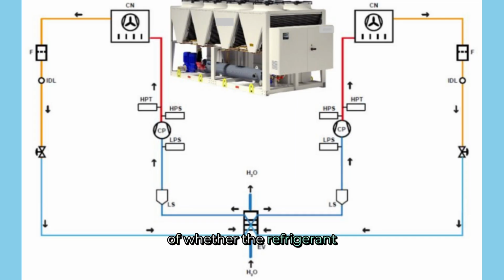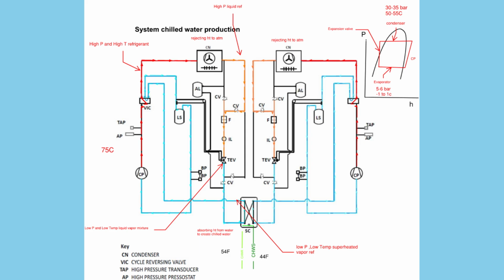Regardless of whether the refrigerant is R410A, R32, or a newer low GWP option, the working principle is the same. The only differences are in the pressures and temperatures at which the refrigerant operates, plus some added safety components in newer systems. Let's walk through the chilled water production process step by step, starting at the compressor.